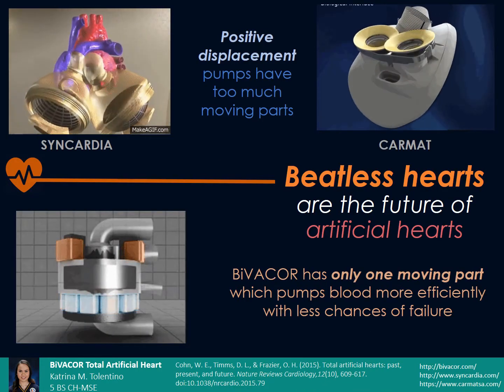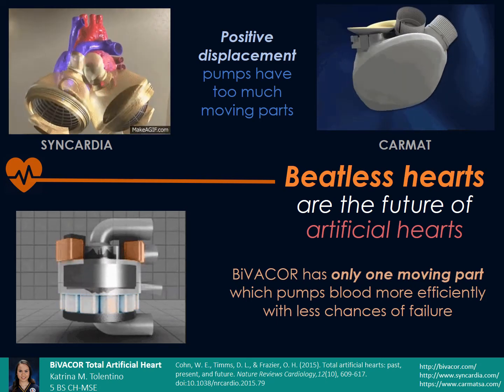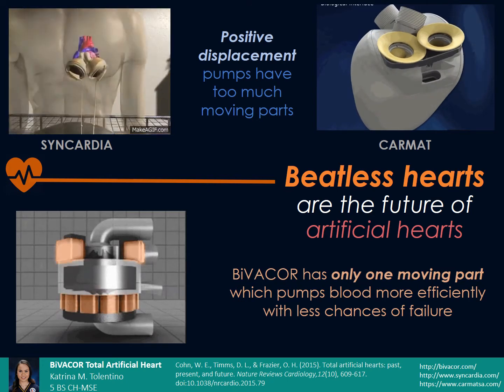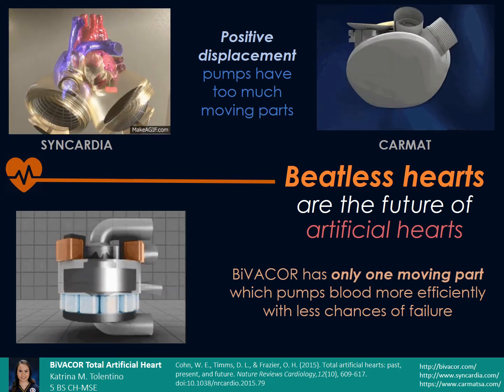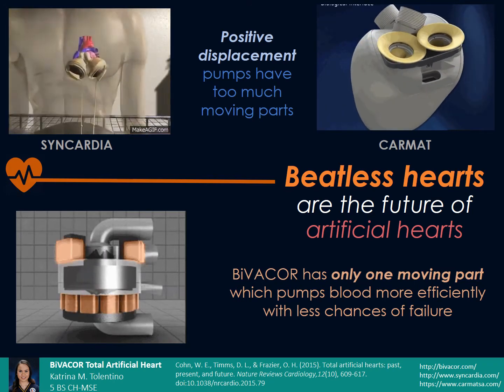Conventional heart pumps are designed to mimic the natural pumping mechanism of a healthy human heart, which is driven by positive displacement — the expansion and contraction of the myocardium. Syncardia and CarMat's total artificial hearts use air and hydraulic fluids respectively to expand and contract a diaphragm which pushes the blood.